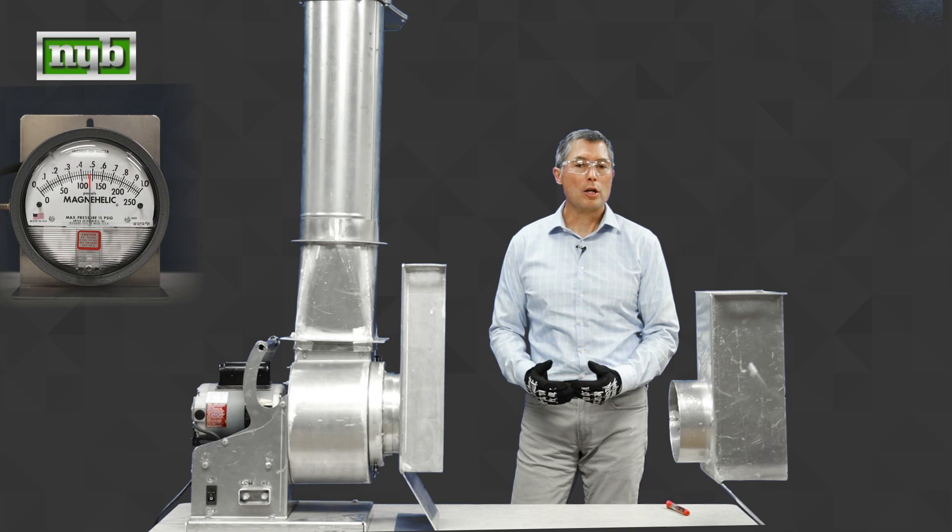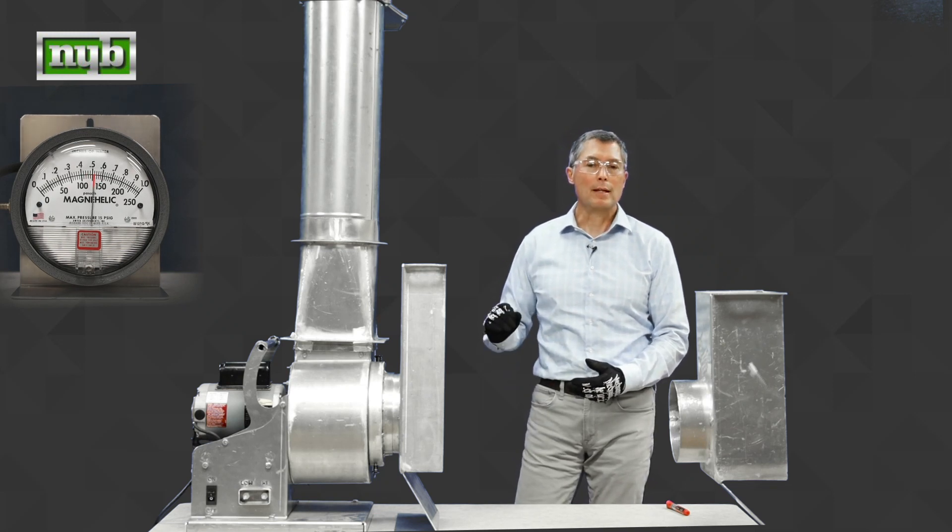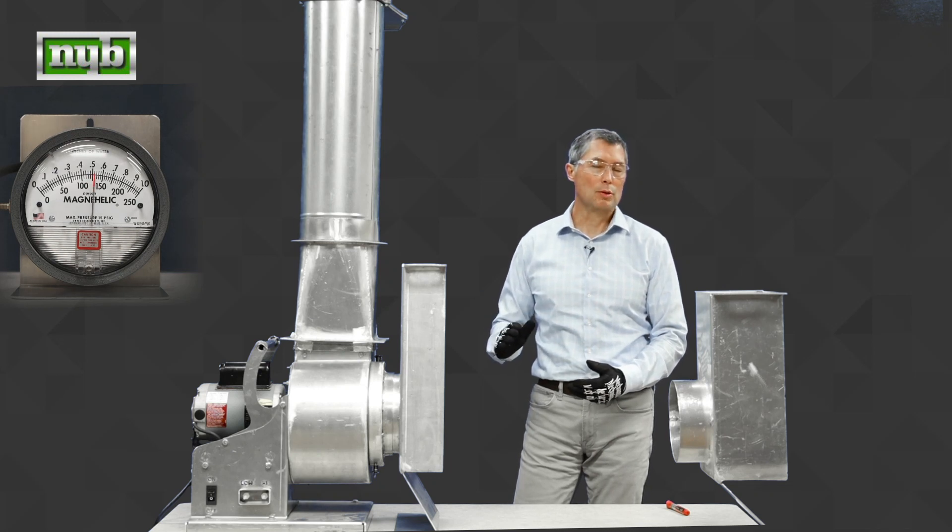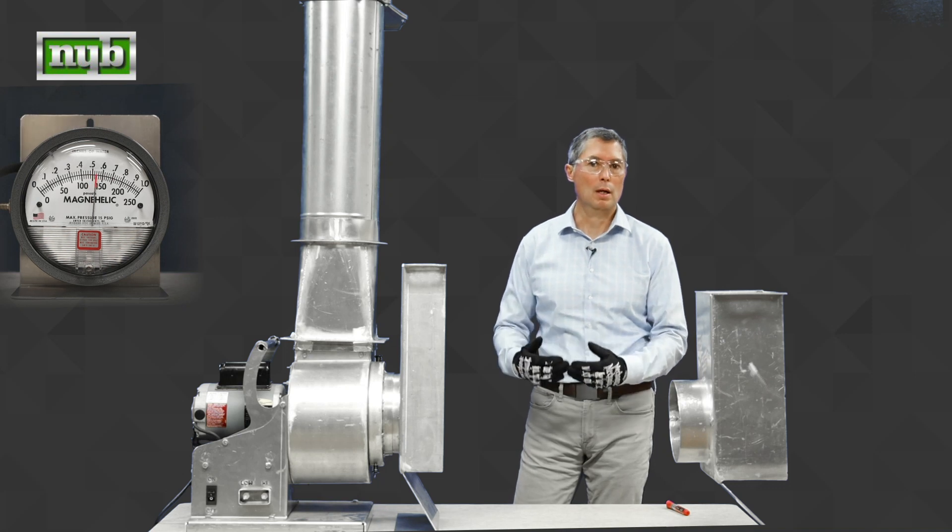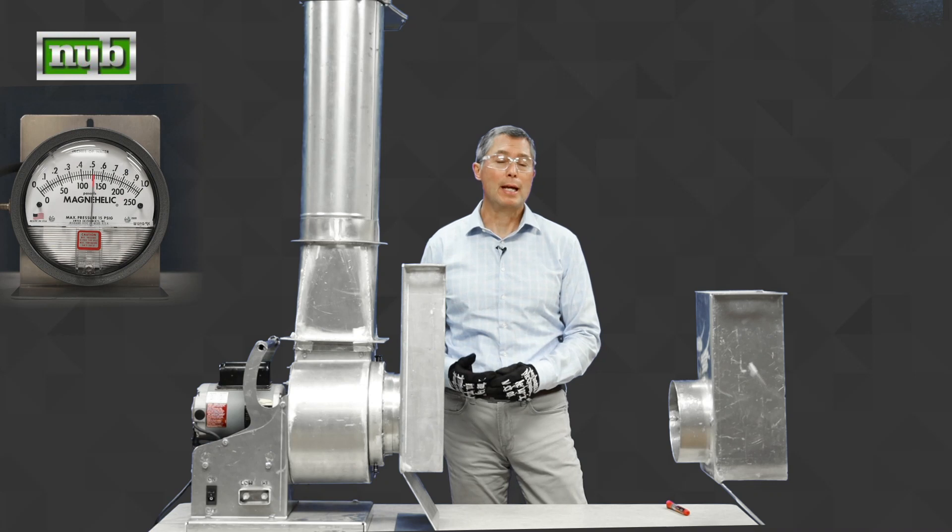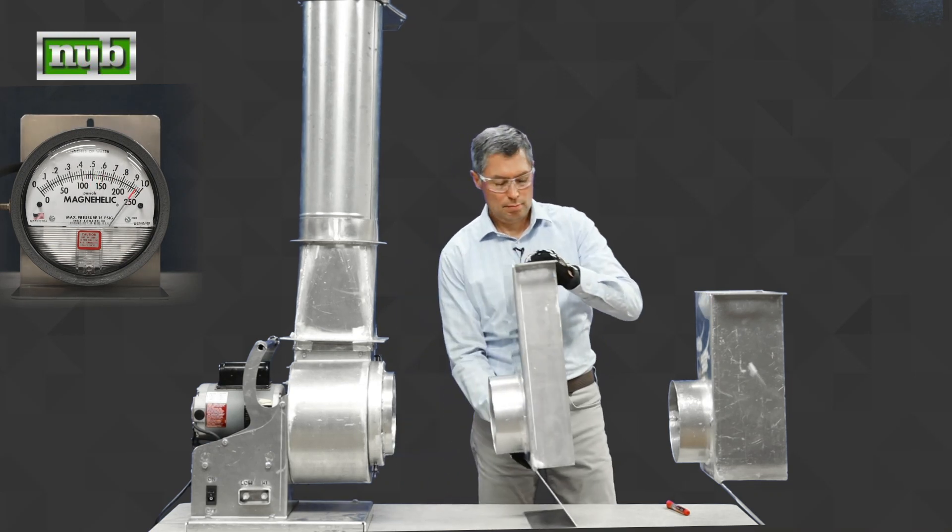And then finally, audibly, you'll notice that there's some droning effects with this. As that needle goes up and down, the sound of the tone, or the sound tone of the fan, goes up and down as well. And that's also an indication that the fan is operating in an unstable region.